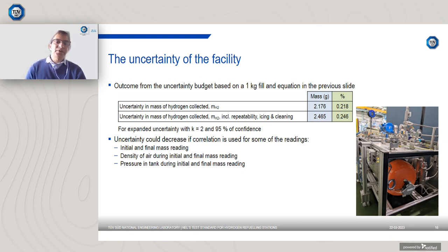This slide shows a summary from the outcome of an uncertainty budget analysis that was carried out for a 1 kilogram fill. Essentially what we found is that for a 1 kilogram fill, which is the minimum measured quantity specified in the R139 standard, the expanded uncertainty of the test rig for k equals 2 is around 0.22%. That is, it can meet our 0.3% target uncertainty. This uncertainty could decrease further, for example, if we were to include correlation, because a number of instruments are used for both before and after filling.